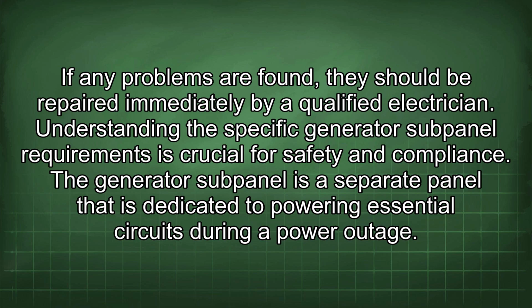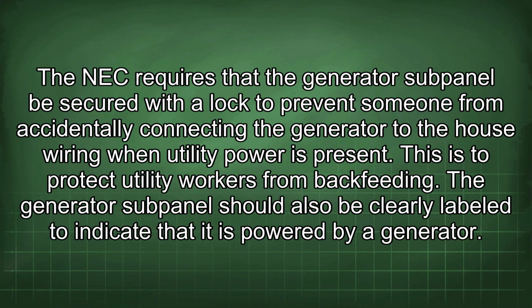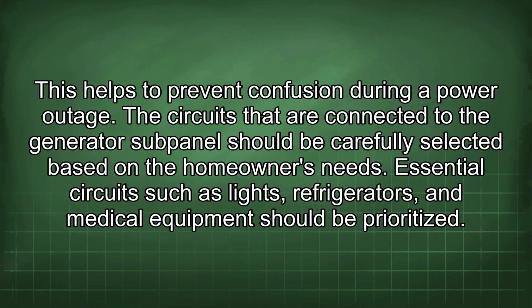Understanding the specific generator subpanel requirements is crucial for safety and compliance. The generator subpanel is a separate panel that is dedicated to powering essential circuits during a power outage. The NEC requires that the generator subpanel be secured with a lock to prevent someone from accidentally connecting the generator to the house wiring when utility power is present. This is to protect utility workers from backfeeding. The generator subpanel should also be clearly labeled to indicate that it is powered by a generator. This helps to prevent confusion during a power outage.